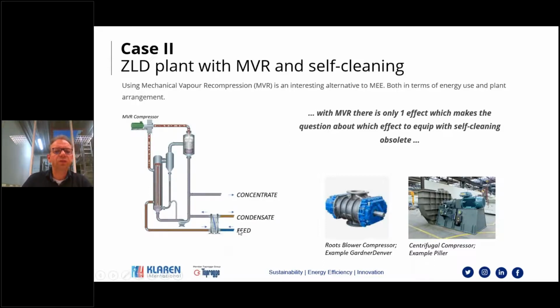But it's also important for an MVR evaporator that you do need to preheat your feed, because if the feed enters too cold, the unit loses too much heat, and that could bring you to failure of the system. So there's always a preheater required to preheat the feed so that it becomes very close to the system temperature. So MVR is positive for energy efficiency, and because there is no discussion anymore about which effect of the multi-effect evaporator plant to equip with self-cleaning.